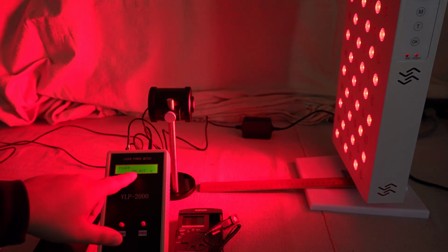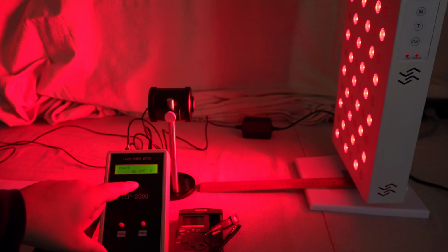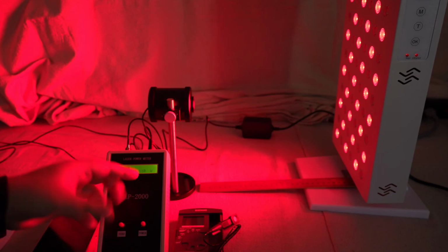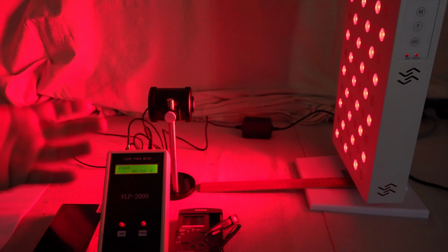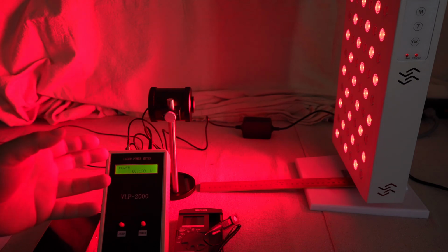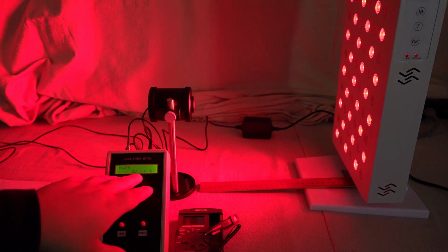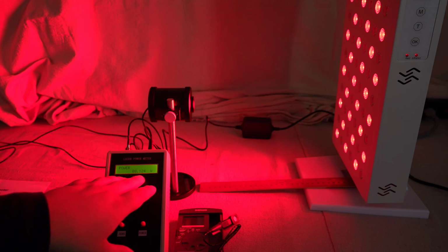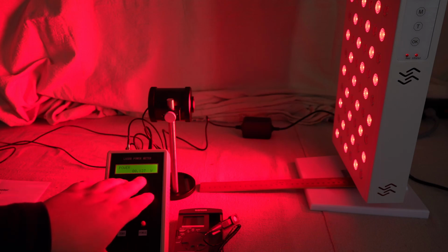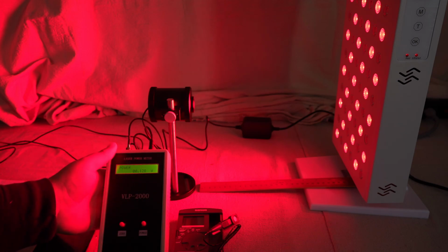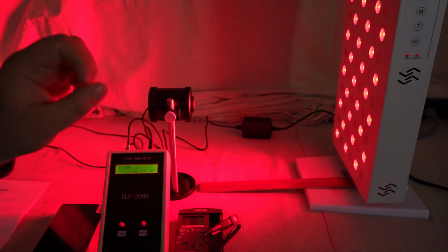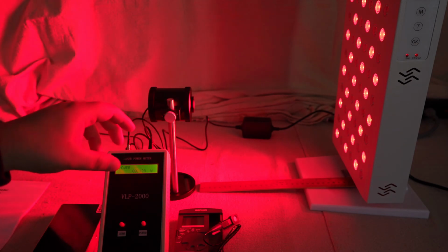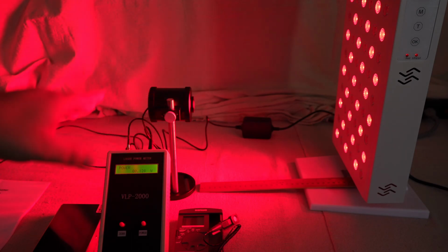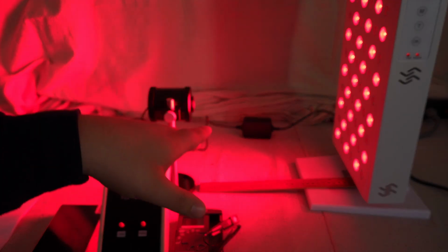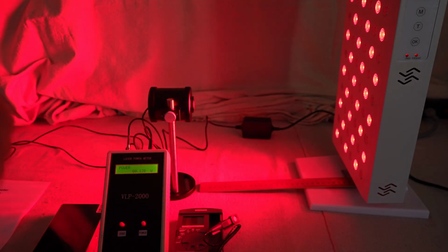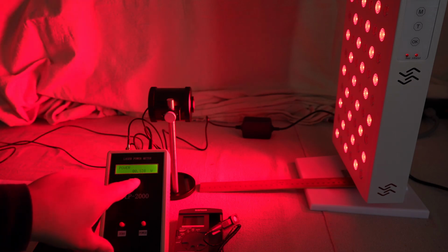And with the thermopile type, it also takes a little while to get the measurement because it does warm up. So again, there are little pros and cons, so you need to think about them with different power meters. This one takes a little bit longer to warm up, but that could be a good thing because if you have pulsing or a lot of flicker, then because it's a slower response, it could be averaging out pulsing or flicker. So again, there are pros and cons to that concept.